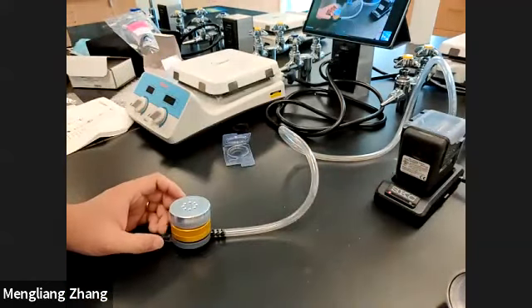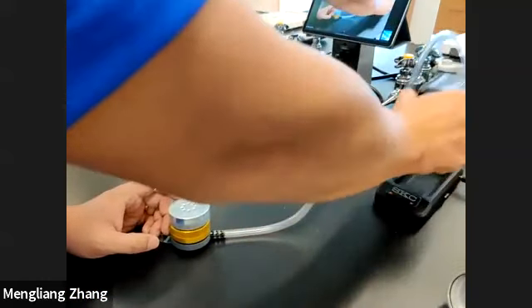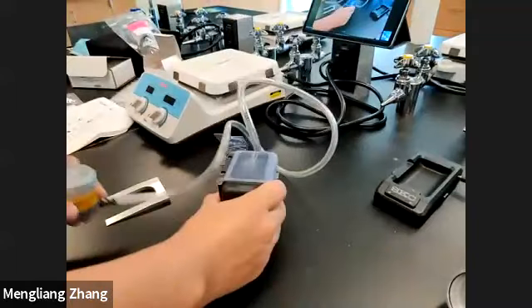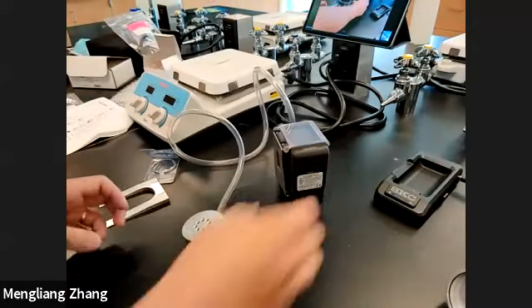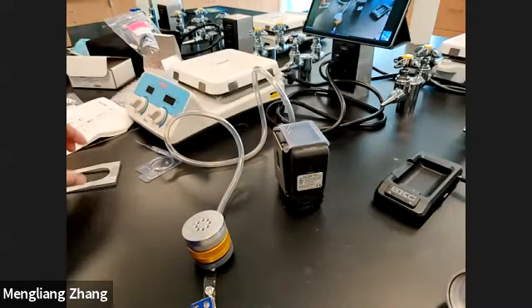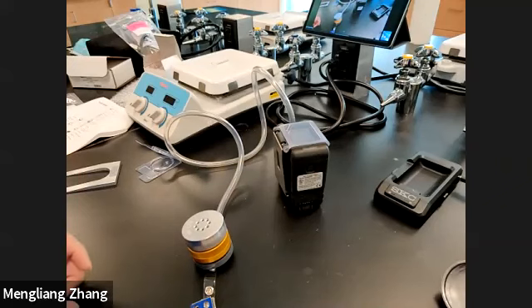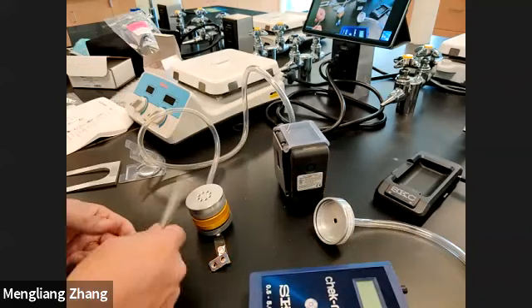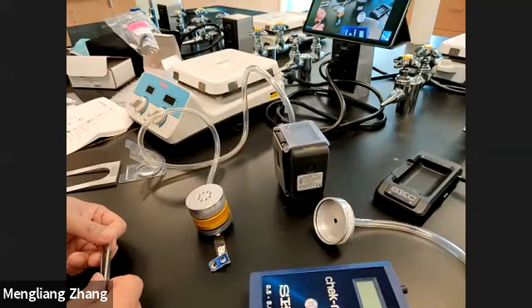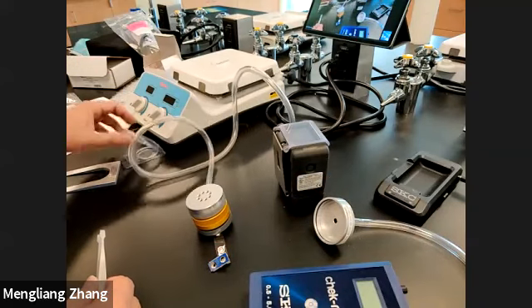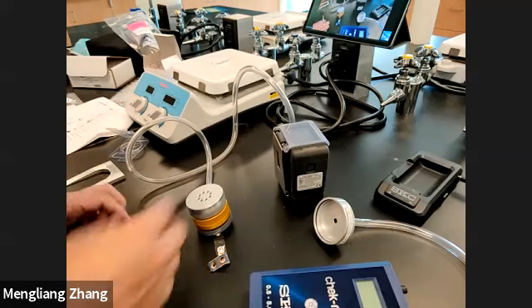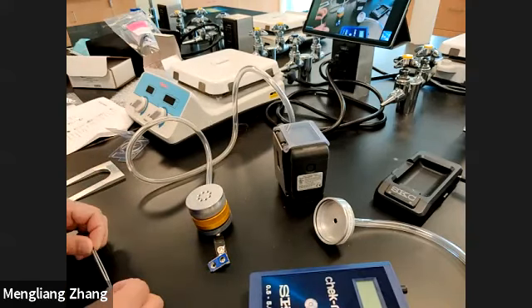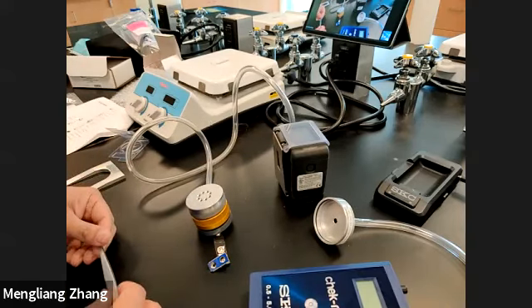Once the pump is fully charged, we can just remove the pump from the charging station. This is the pump. Before we use the pump, we also need to calibrate it. According to the manual, for this impactor, the desirable flow rate is 3 liters per minute. So in this case, we need to calibrate the pump to provide the airflow at 3 liters per minute.